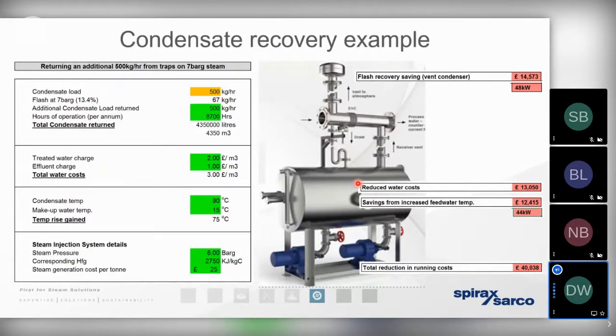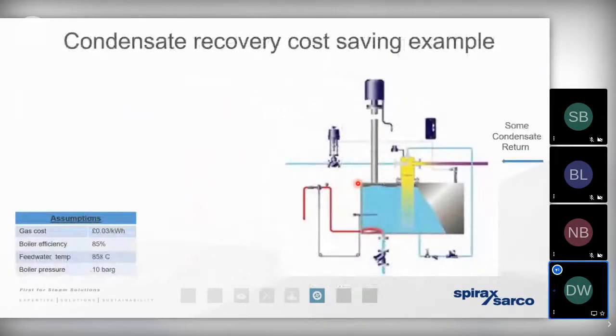And the calculations are relatively easy to undertake. If we know the pressures, temperatures, and mass flow rates that we're faced with, combined with the cost of steam generation for our application, that information can be very, very useful for helping us to drive a project forward to keep the rate of condensate recovery at its highest and most attractive point. So I want to run a very quick cost-saving example for you here. I want to start off by looking at the cost of steam that we have.